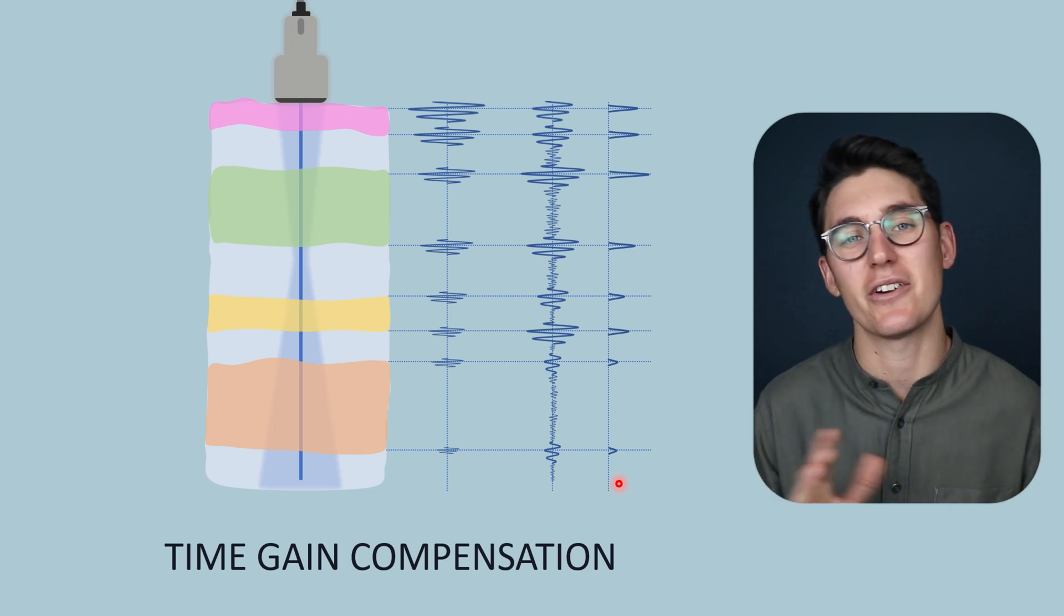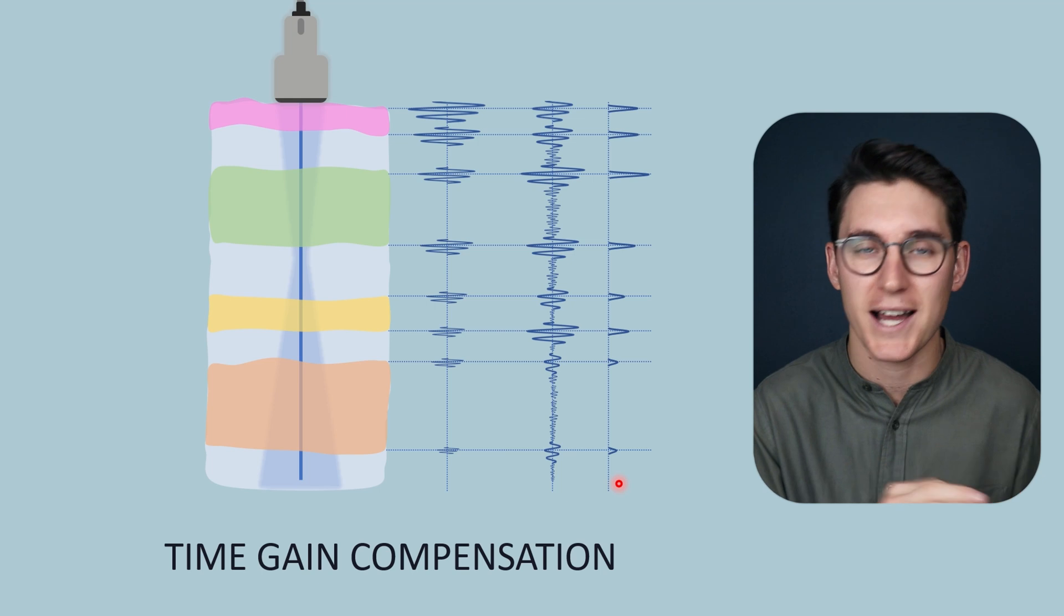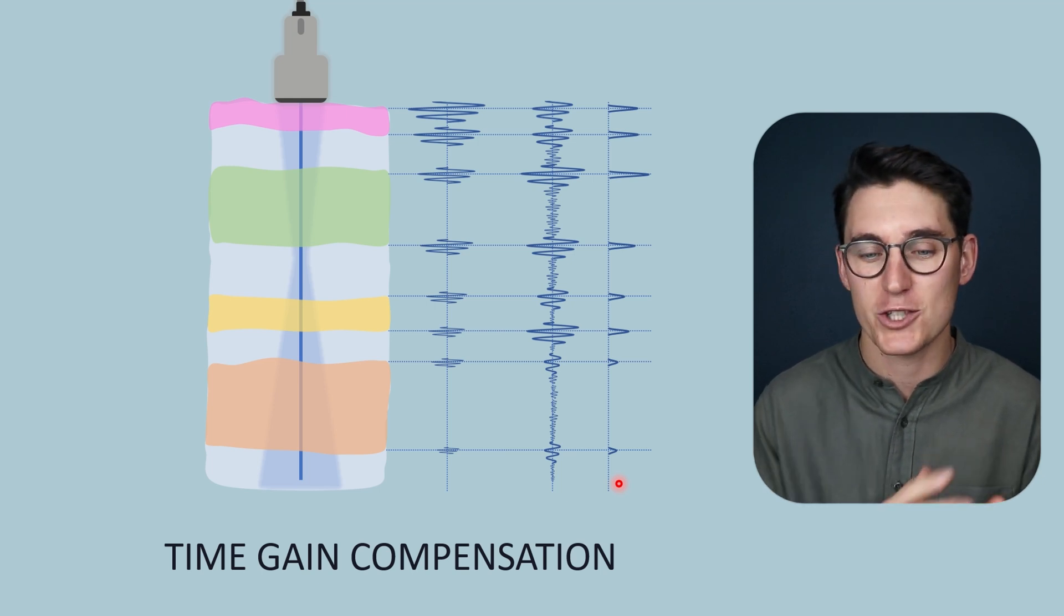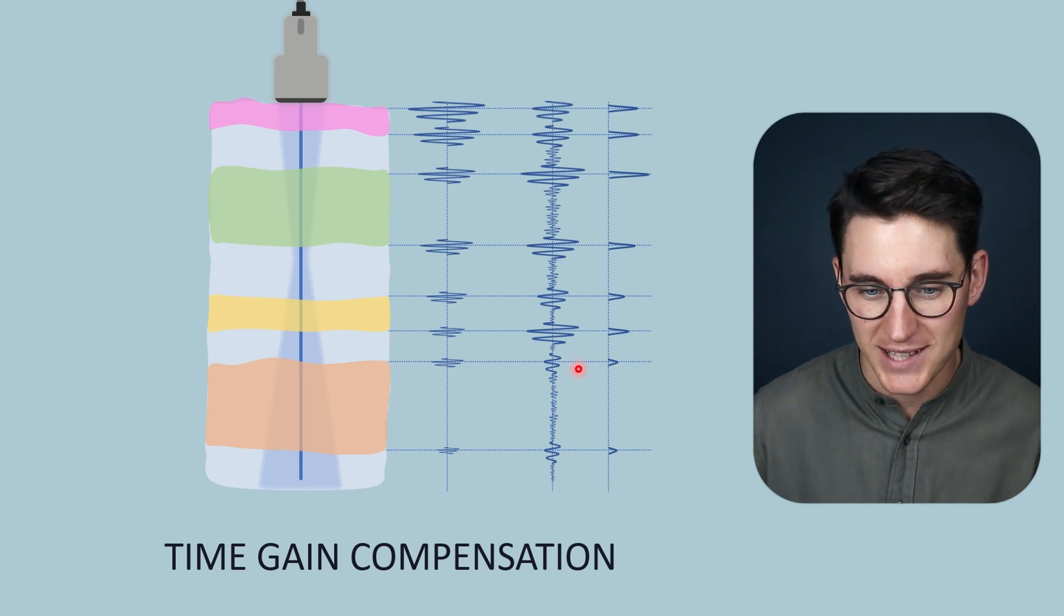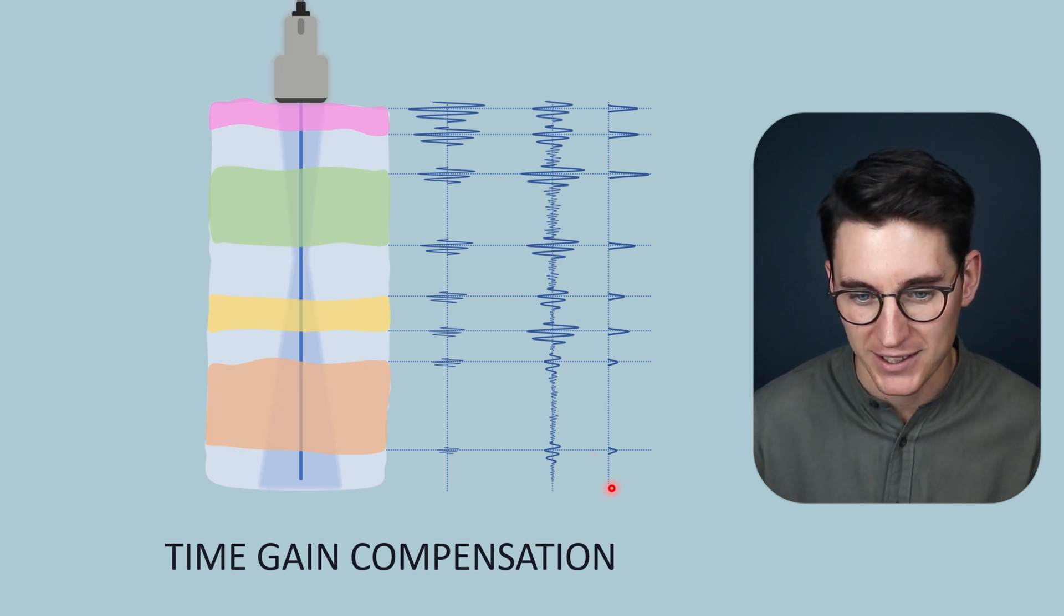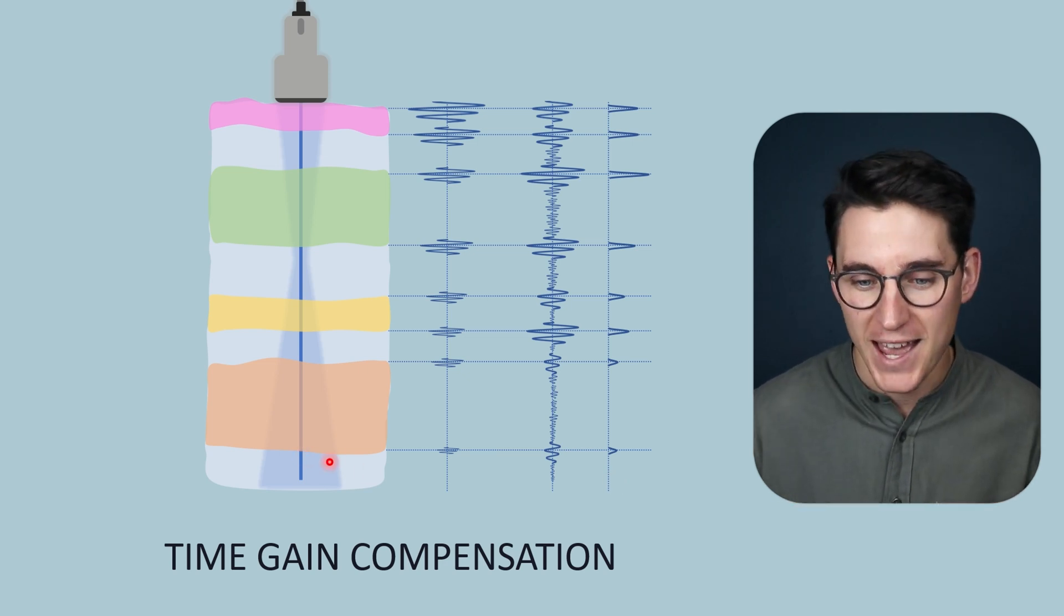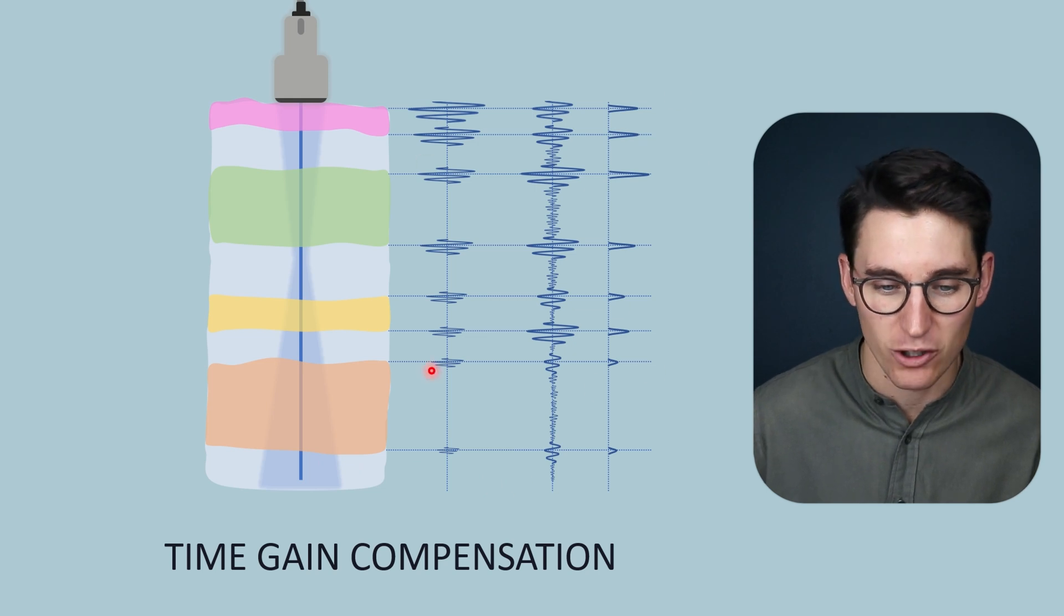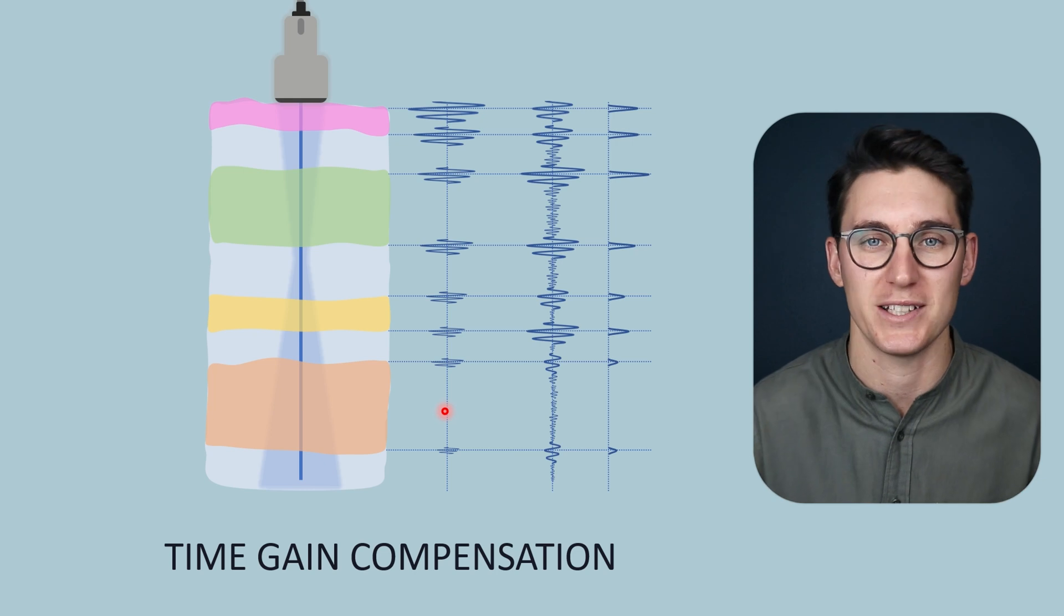Now you may have heard of this in various different forms. Often people call it depth gain compensation or time varied gain. You may have also heard of swept gain. These are all synonyms. They all mean the same thing. So how do we go about ensuring that this A-mode signal that we get back truly reflects the differences in acoustic impedances at tissue boundaries and doesn't integrate the loss of intensity as the incident ultrasound beam travels through tissue?